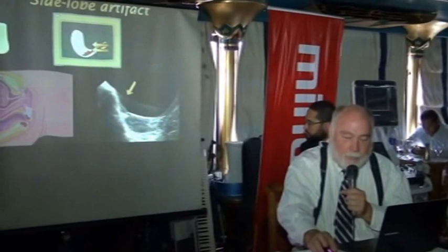Side lobe artifact: when we use the beam, we have a tendency to think that the beam is just pencil thin, and it just does one line at a time. And that's not completely correct, because alongside the beam, you may have some side lobe beams, which are slightly deviated to the side, and the intensity of the side lobe beams is not very high, maybe 1%, 2%. And so usually, if you add 1% gray or 2% gray to the image, it doesn't make a difference. But there are some situations where it does make a difference. For instance, if you look at the bladder, adding 1 or 2% gray over the black of the bladder makes a difference. And a long time ago, many of these patients were referred for having urinary tract infection or debris or pus in the bladder. This was absolutely incorrect.